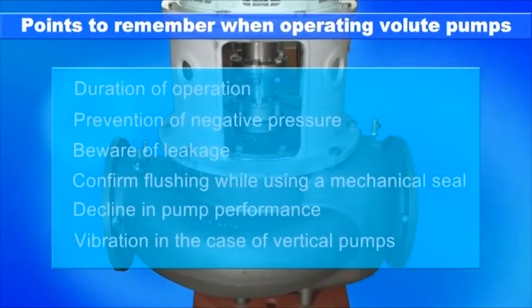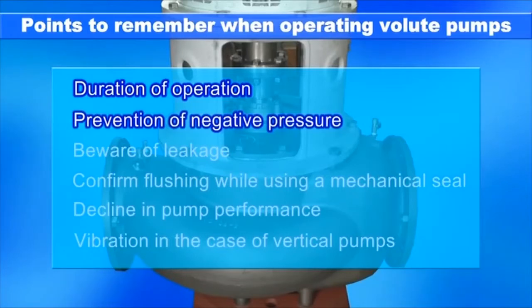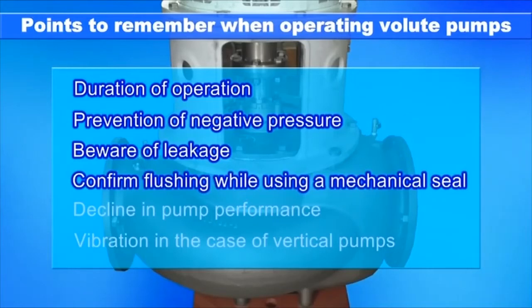The following precautions must be taken in operating volute pumps: consider replacement of ball bearings depending on duration of operation, beware of negative pressure operation to prevent cavitation, during operation beware of leakage from the gland, and when using a mechanical seal, beware of damage to the seal and confirm that the flushing liquid is flowing and the mechanical seal part is clean.